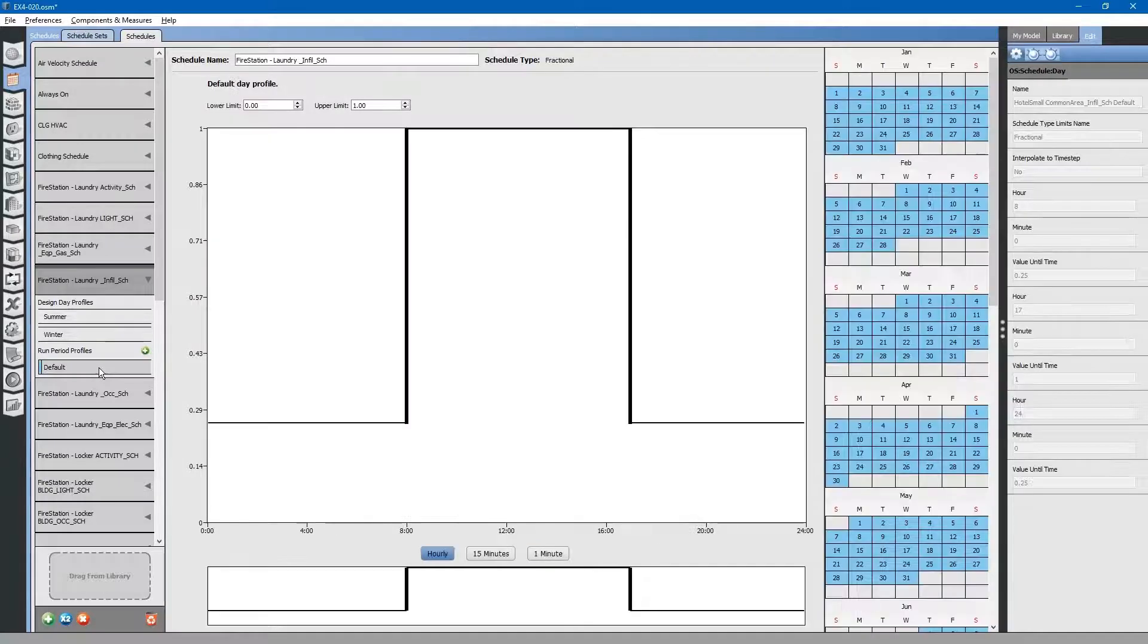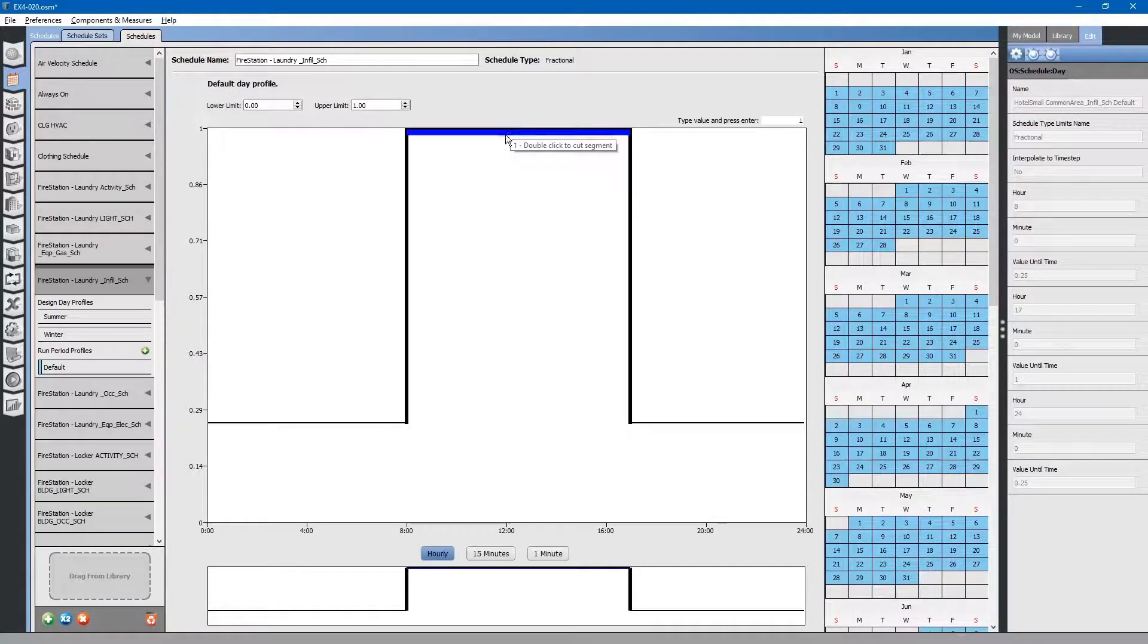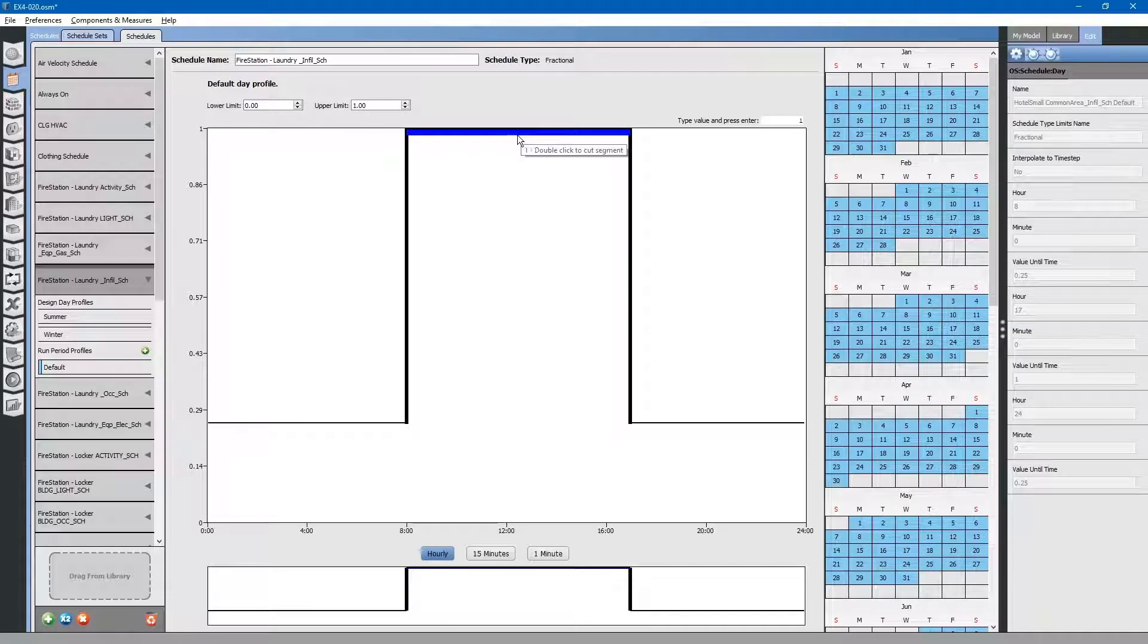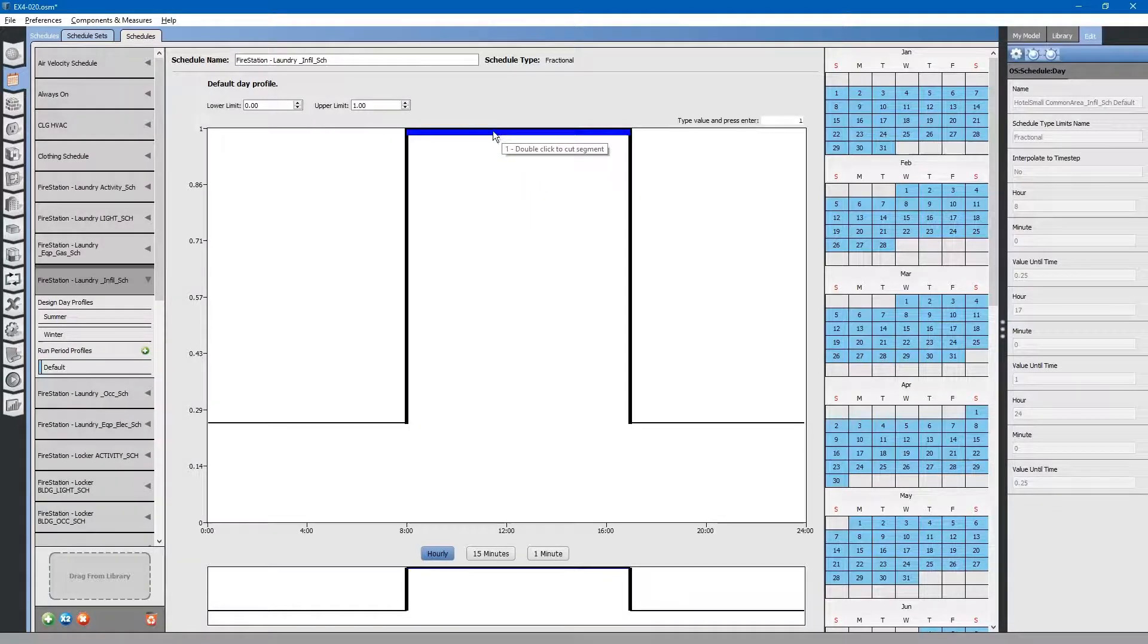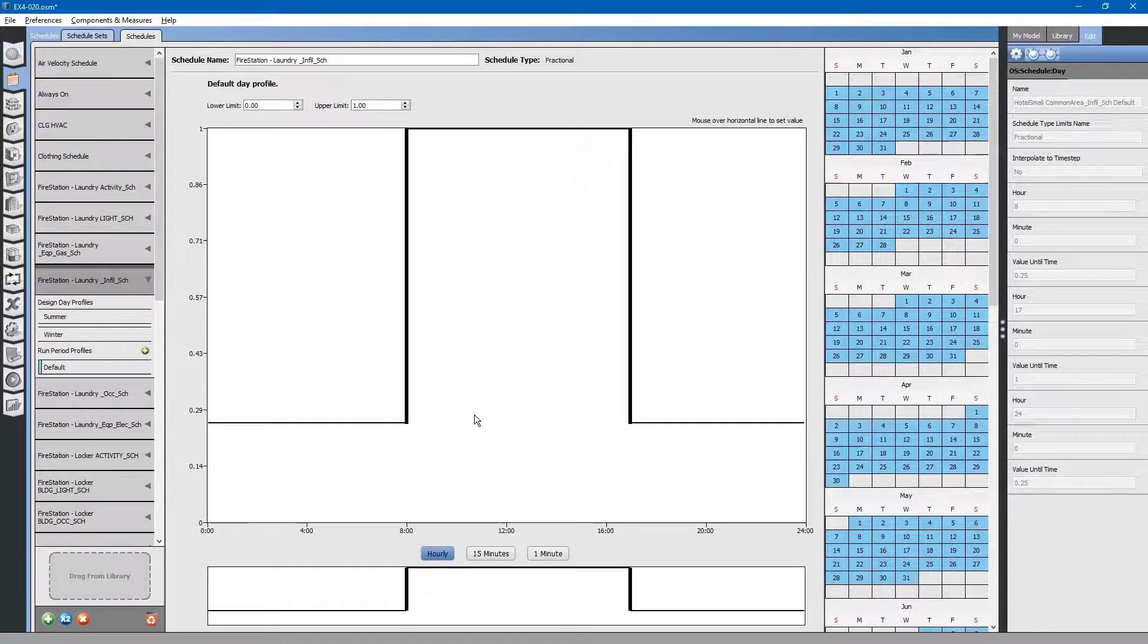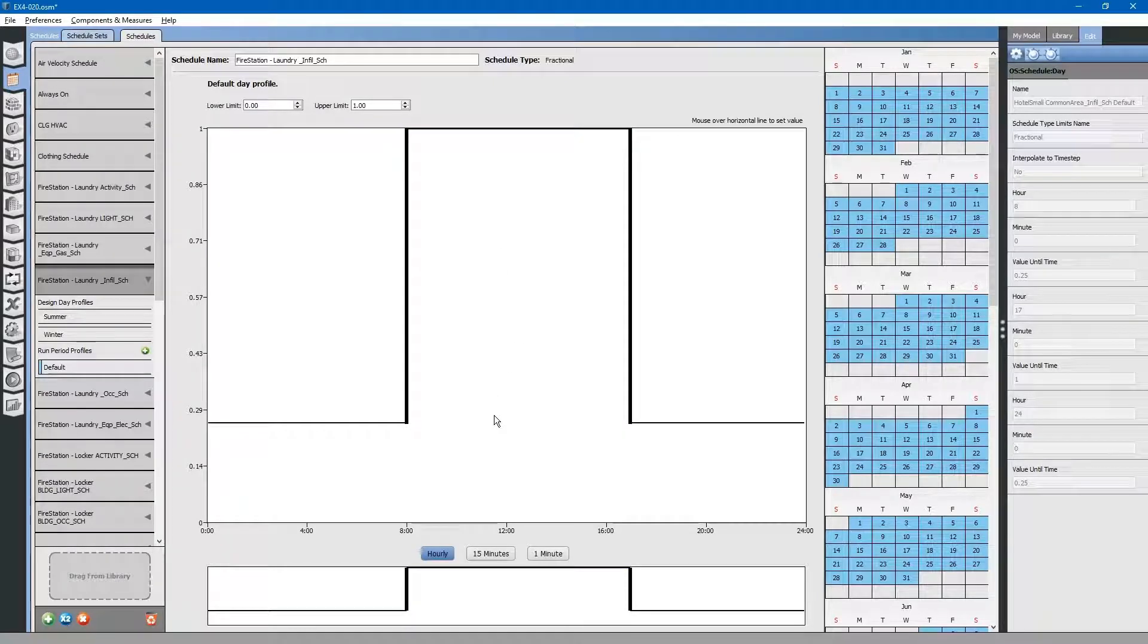We want to make sure that is at 100% for summer and winter for sizing the zone equipment or the HVAC equipment. Looking at our schedule, during the occupied hours it goes to 100%. That ensures that the infiltration flow will be 152 CFM during occupied hours.